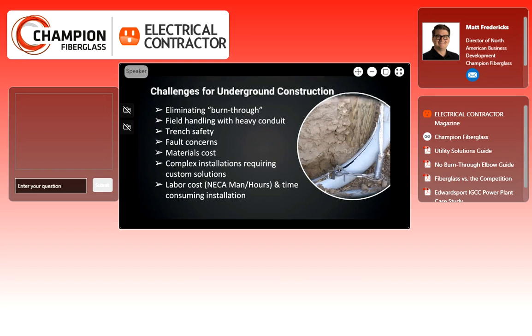So for many years, engineers have been specifying galvanized rigid or PVC coated sweeps. You can actually use a fiberglass sweep as well. Those don't burn through, so that would be something to consider. If you're using a GRC sweep, or especially a fiberglass sweep, that's going to reduce the overall tension and sidewall pressure when you're pulling through a sweep. But if you've ever burned through a sweep, it's a real bummer. So make every effort to make sure that you're not going to burn through one of those sweeps.